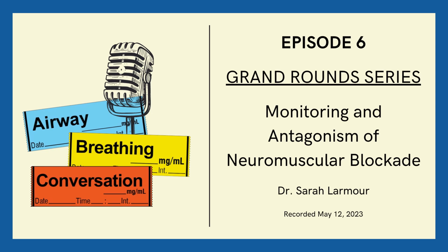But if we want to do EMG, which we need in those cases where the arms are tucked, the StimPod NMS 450X actually is a dual system with both AMG and EMG capabilities, which we just have never had the EMG electrodes or cables here. The EMG electrodes are one-time use and cost about $30 a piece. The nice thing is that because you can use the same monitor for both AMG and EMG, you can take advantage of the cost savings of AMG for many cases and then use EMG only in robotics cases or other cases where the arms would be tucked. An EMG cable that's compatible with our Philips monitors, so that you can have your quantitative results displayed on the anesthetic screen on that right side, is about $580.